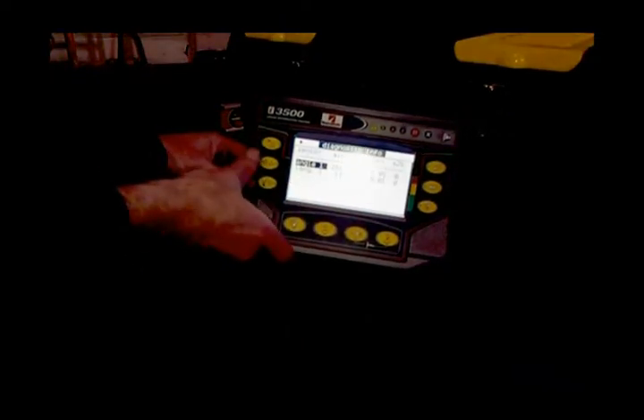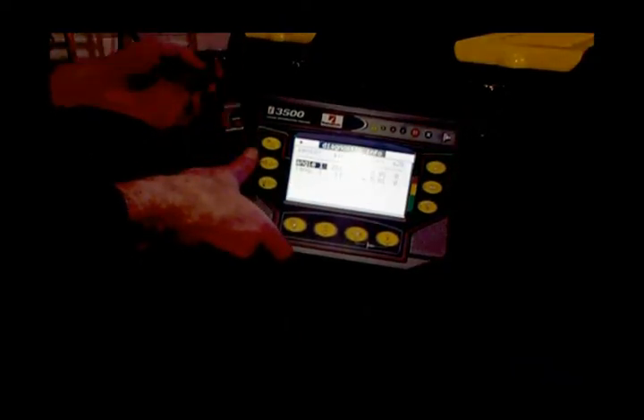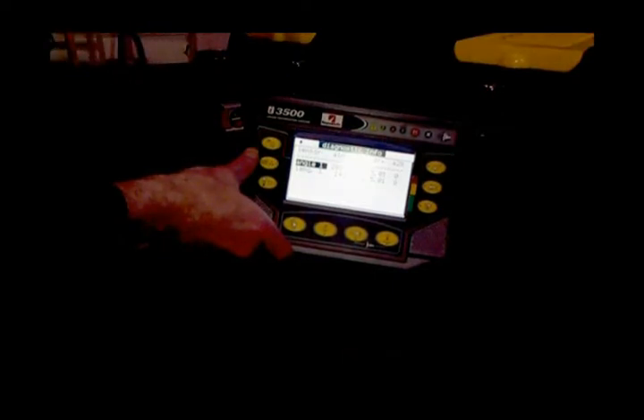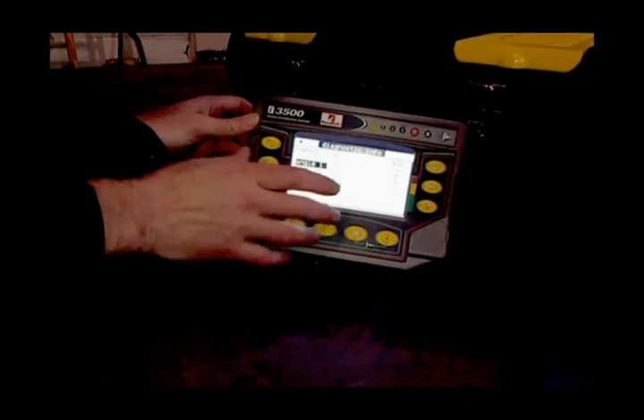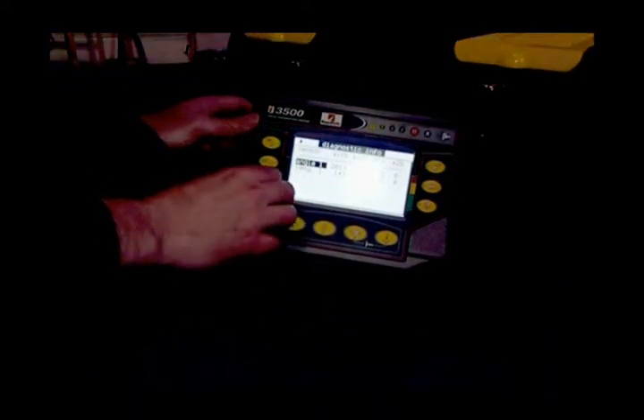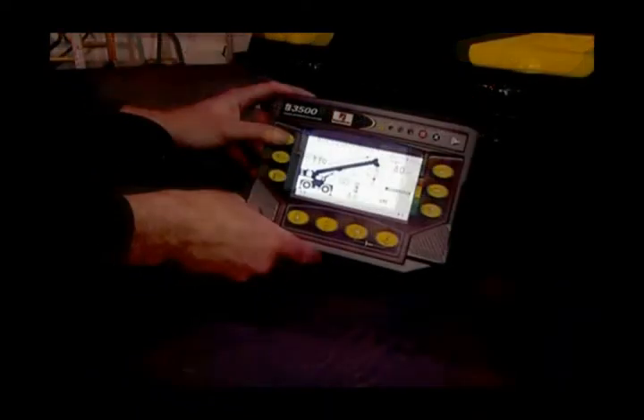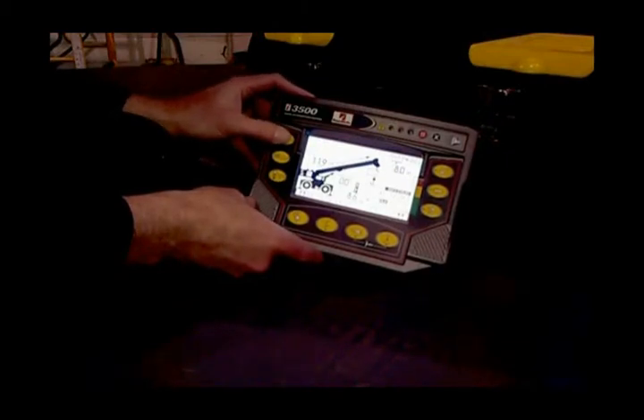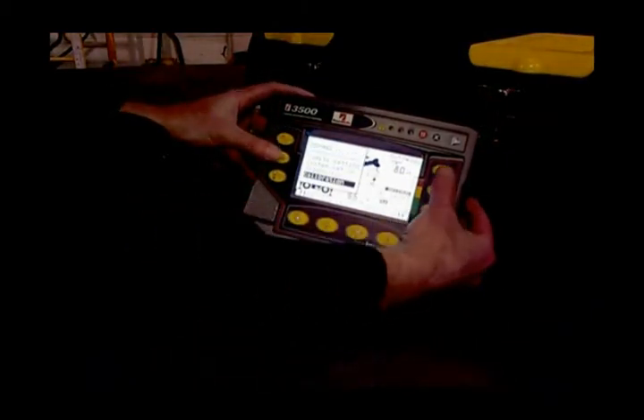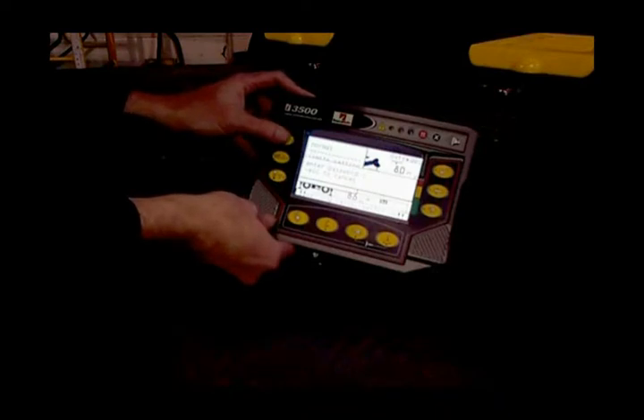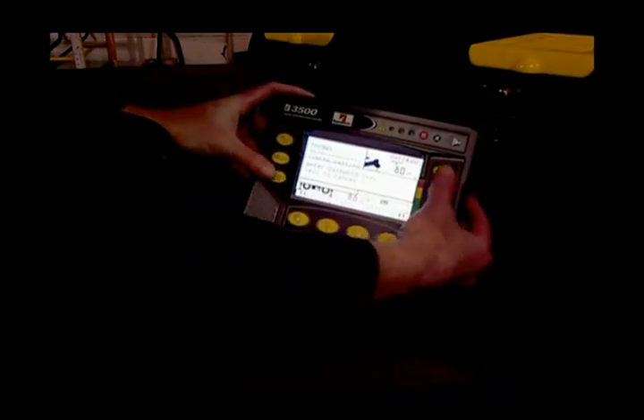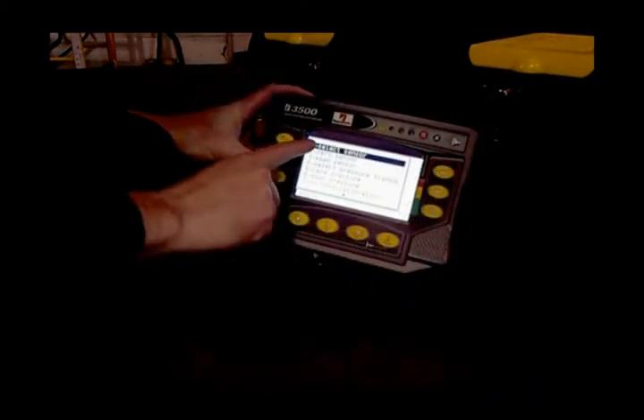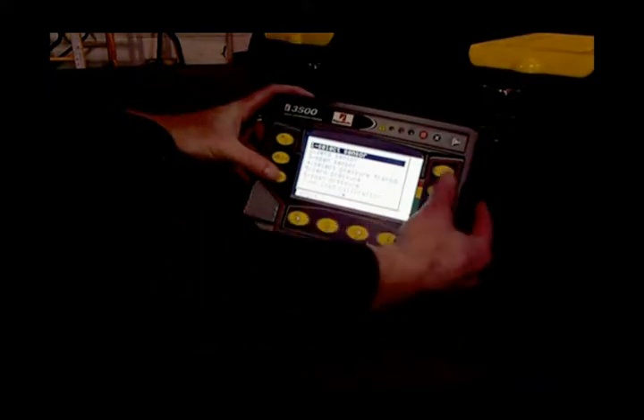At that point, you would then engage the gears in the cable reel and secure your potentiometer bracket in place. After you do that, we can go ahead and begin the calibration process. So what we want to do is go over to calibration mode now and enter the password 1, 2, 3, 4.